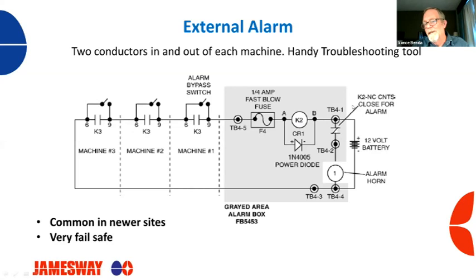So anytime you're connected to normally closed contacts, and for anybody that doesn't understand the concept of normally open, normally closed, that's what happens when this coil has no power on it, these contacts are going to close. Normally open, if this relay didn't have power, it would be open. Working on the series wired alarm system, we're wired in normally closed contacts. So if anything happens out here to stop the flow of electricity to this coil, you fall on normally closed contacts and this horn is going to blow.